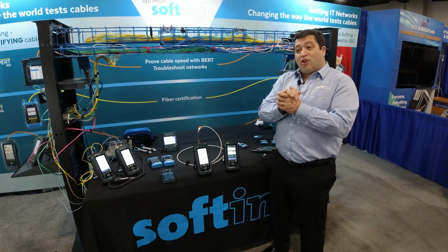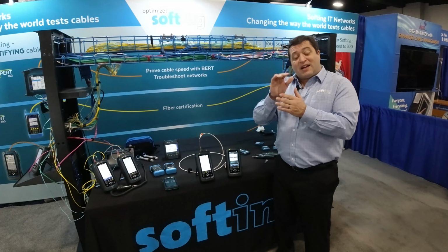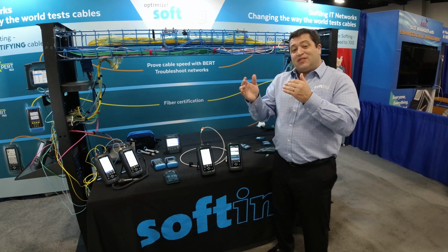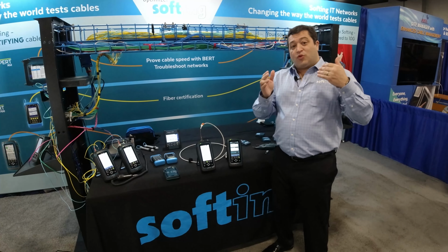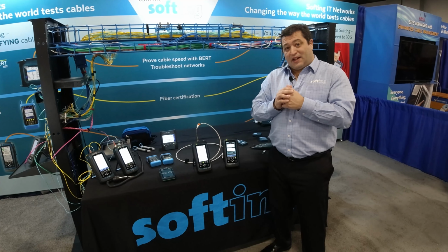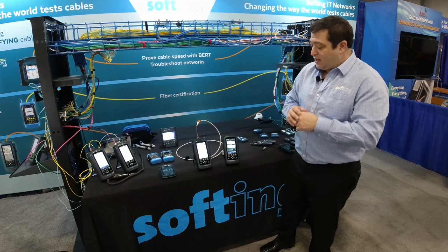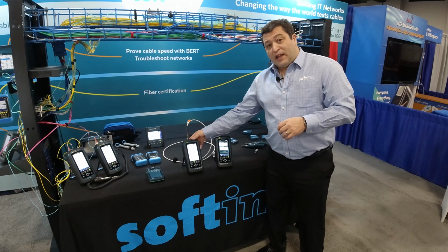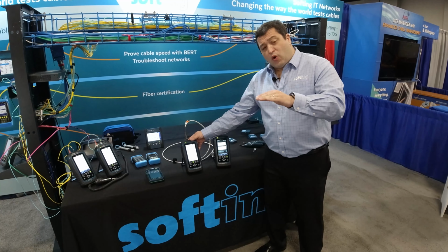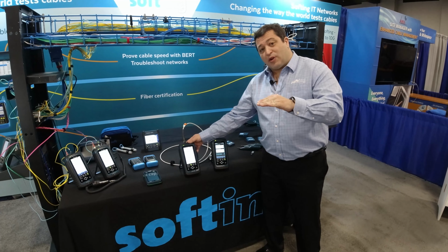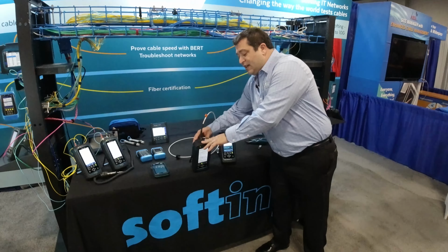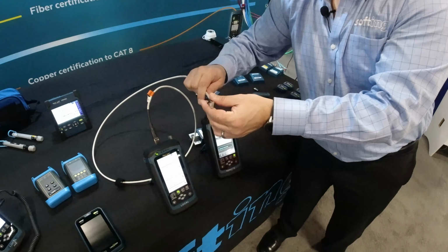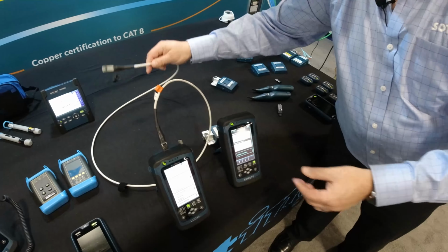These type of links are going to wireless access points or cameras commonly. The point to that link is that there's no equipment cord between the device and the end of the link, okay? So here's the connecting hardware. On the local unit, you've got a permanent link adapter. Now that's common equipment that is in the Wire Xpert test kit, okay? Permanent link adapter and permanent link reference cord.